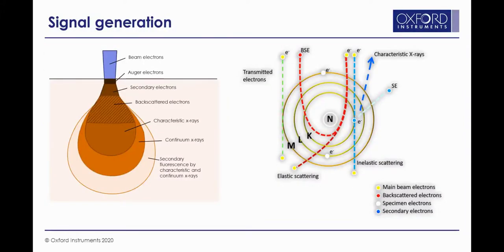These diagrams help explain what happens when the electron beam interacts with a sample. On the left, you can see the beam interacting with a specimen and a range of different signals being emitted from different depths within the sample. These include secondary electrons and backscattered electrons commonly used for imaging, as well as characteristic X-rays — the ones we detect using EDS — and continuum or background X-rays, as well as a variety of other fluorescent signals.